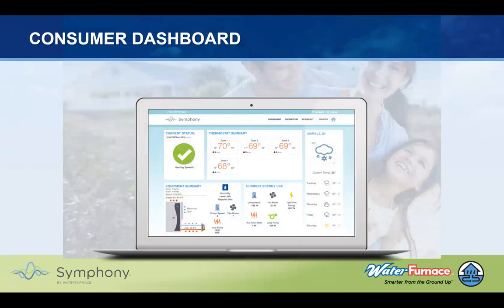We also provide a dashboard that can be seen through a tablet, or as you see here, a PC. The information we provide, starting in the top left corner, is the actual status of the piece of equipment and how it's operating at present. It shows all of the zones on that particular system. It then shows an equipment summary, which is what you would see on a thermostat, such as the humidity level and your humidity set point, your fan speed, your compressor speed, and whether the auxiliary heat is on. It shows you the loop temperature in, and also the supply and return temperature of your piece of equipment, along with the energy monitoring, which I'll spend more time on in just a minute. And then it gives you the weather for your given location.